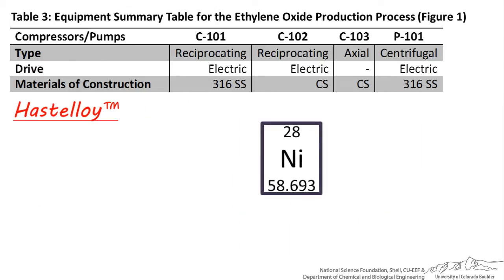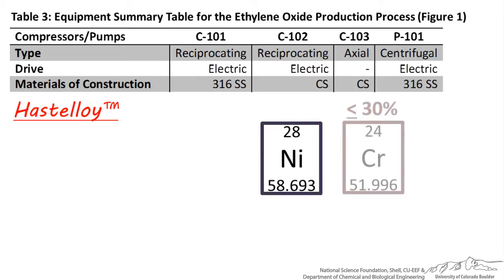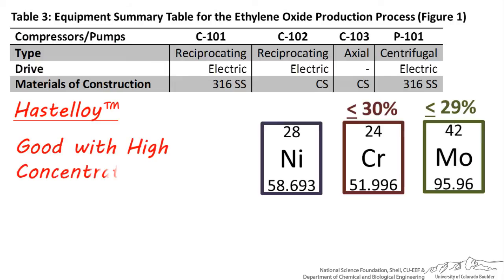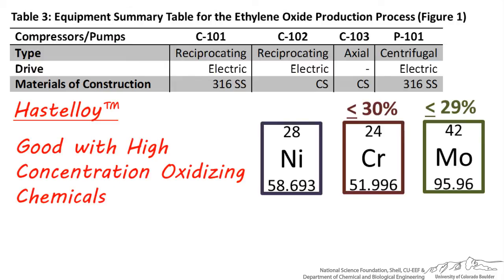Hastelloy is mostly nickel, with up to 30% chromium and up to 29% molybdenum, along with tungsten, iron, cobalt, and other elements. Hastelloy is good to use with high-concentration oxidizing chemicals, such as peroxides, nitric acid, and sulfuric acid.